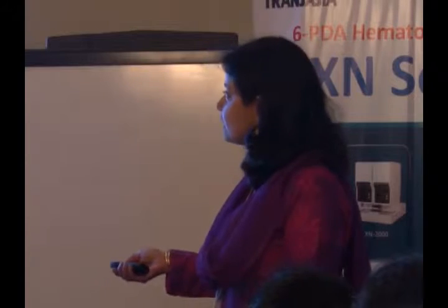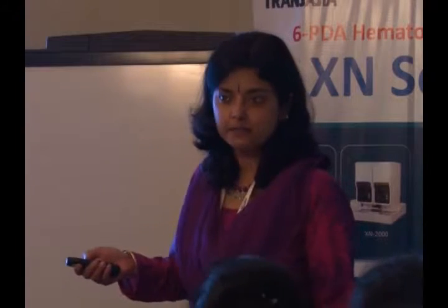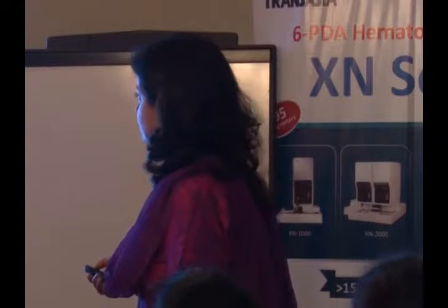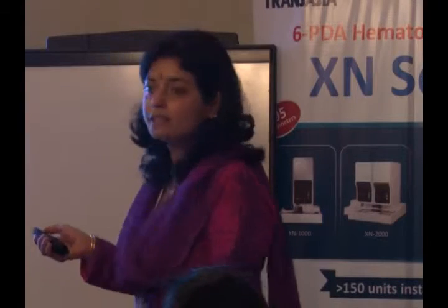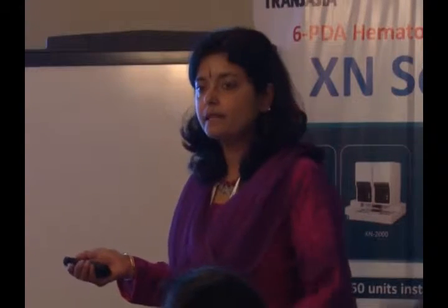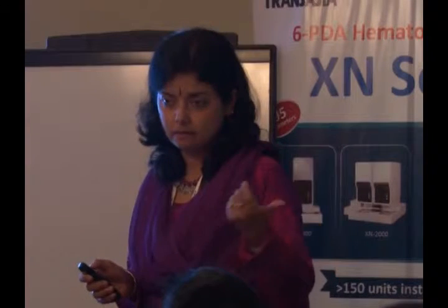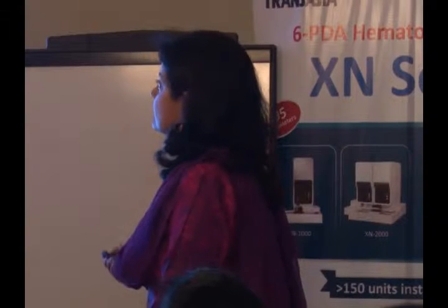So where do I start? Now we are talking of novel parameters, right? So where have I started using them in my practice? There is a new reticulocyte channel, the RET channel. The RET channel I had in the XE2100, here again in the XN. So what is the RET channel doing?